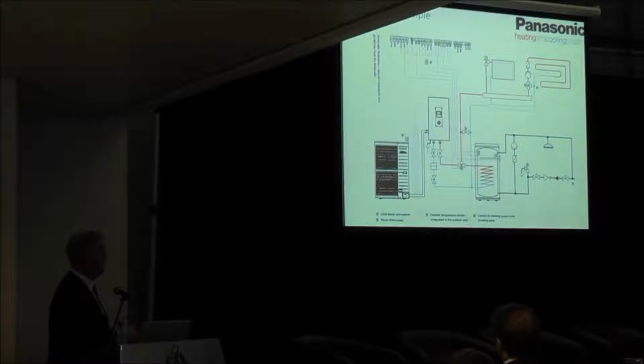With a split system, the heat exchanger is located inside the house. And again, the heating side and the domestic hot water is exactly the same. There's no difference. The only difference is you have refrigerant pipework onto the outdoor unit. This does then come under the whole F-gas regulation, that a certified F-gas engineer has to do the final connections, has to pressure test the system, has to evacuate the system, and then has to open the valves. There should be no need for the engineer to add refrigerant to the system.